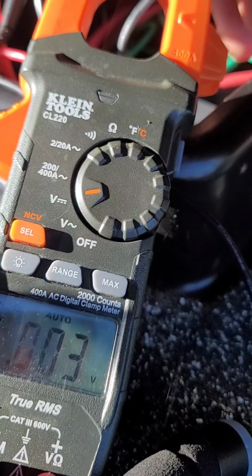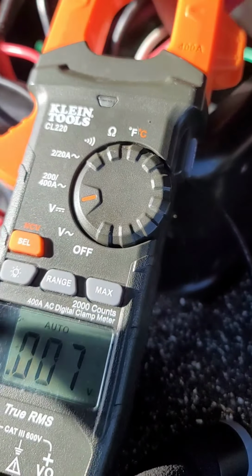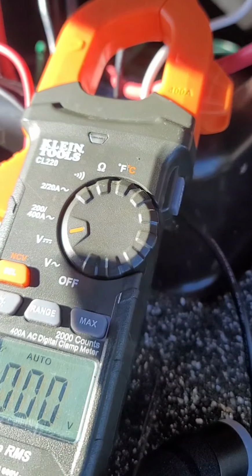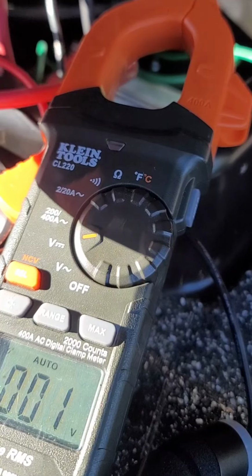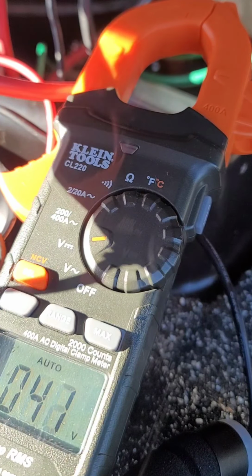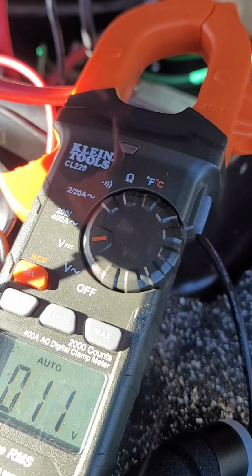On our second string jumper, we should be getting at least 5 volts. There's 5 optimizers, you should be getting 5 volts. When we pull the voltage from the jumper from the array of the 21 using the 5 panels, we do not get 5 volts. Real simple. That means that 5 of the optimizers are no good.